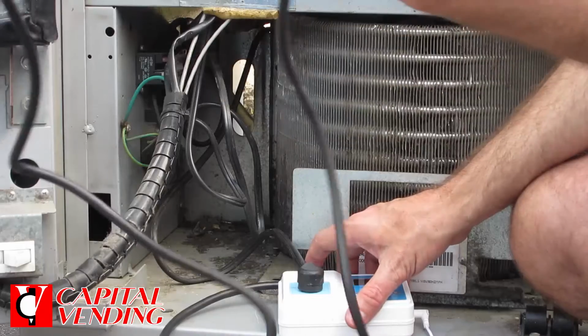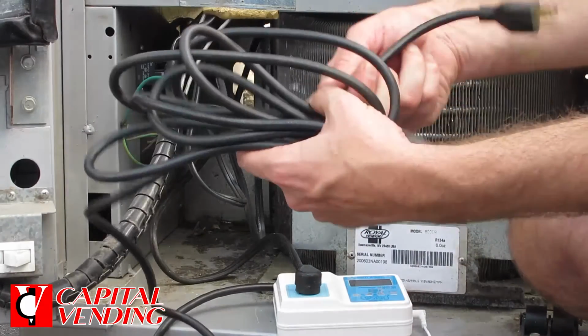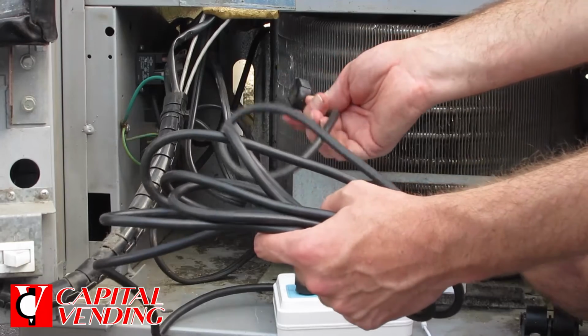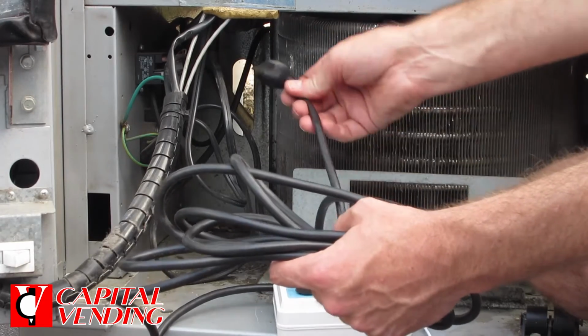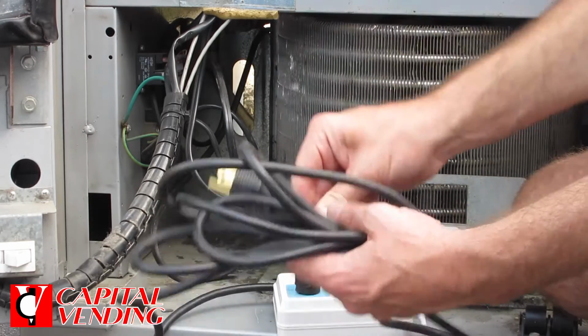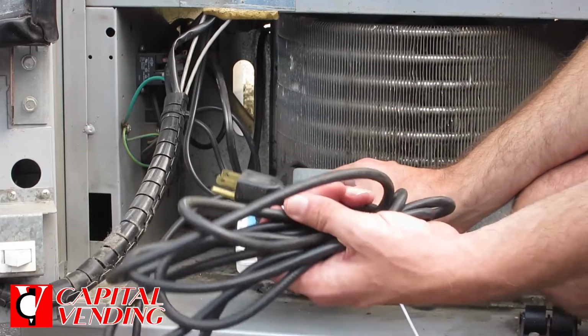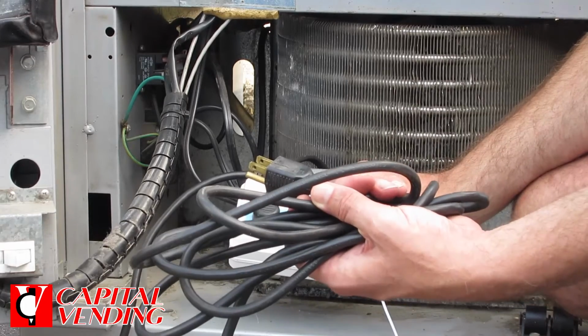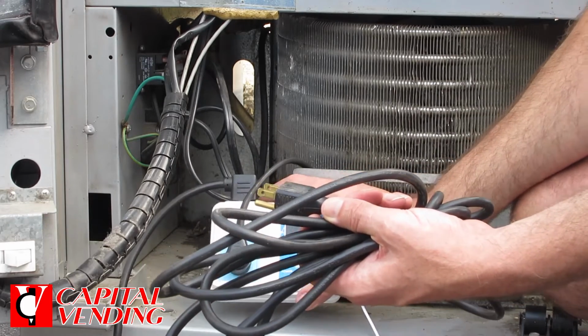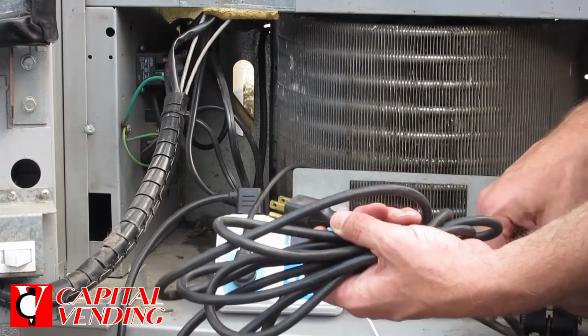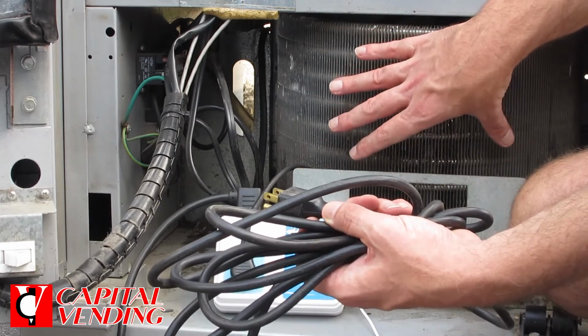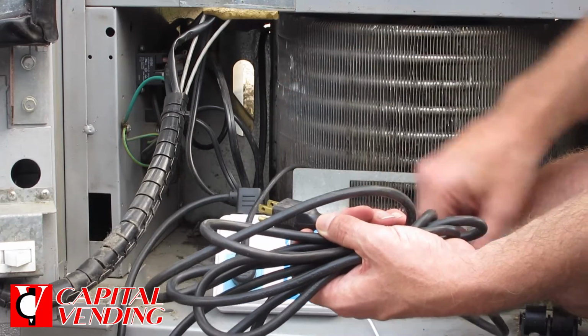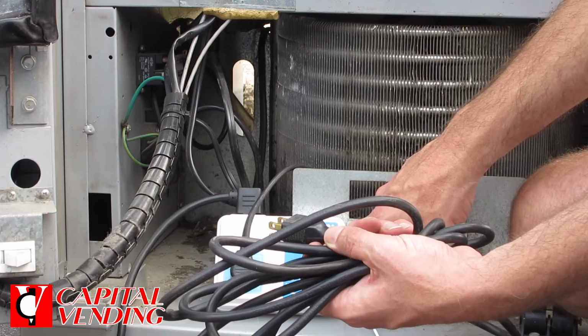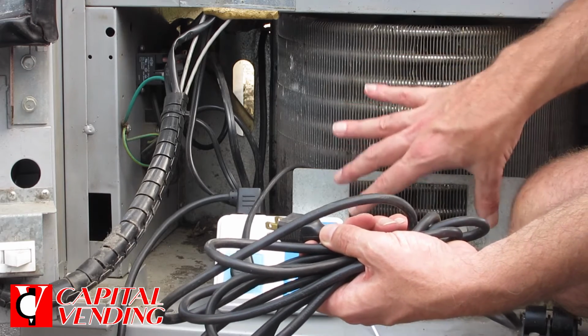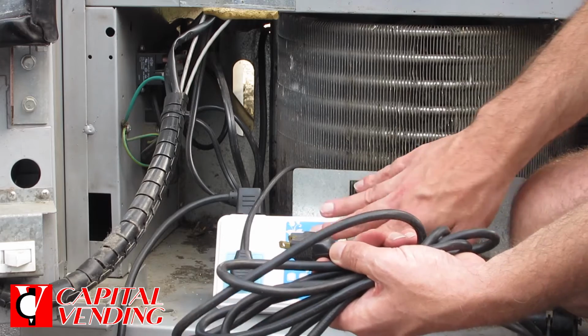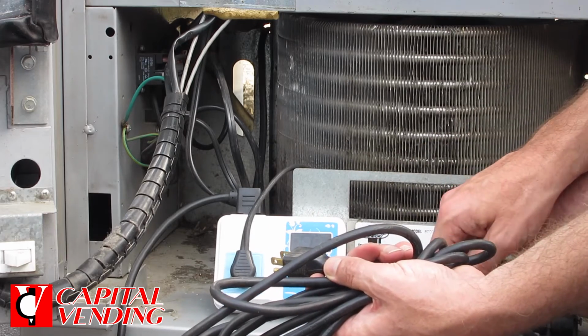This very heavy-duty long cord is included with the kit, and for this particular machine, the stack machines are typically easy to feed it through the back—there's plenty of access holes to do that. But what I'm going to do right now is plug this into a wall outlet just for testing, because if the compressor doesn't come on, then I know the problem is with the compressor unit or the refrigeration system and has nothing to do with the electronics. So one of the big features of this is it helps you rule out whether it's the system or the electronics. If it is the electronics, this can be used temporarily until you've replaced the bad part.